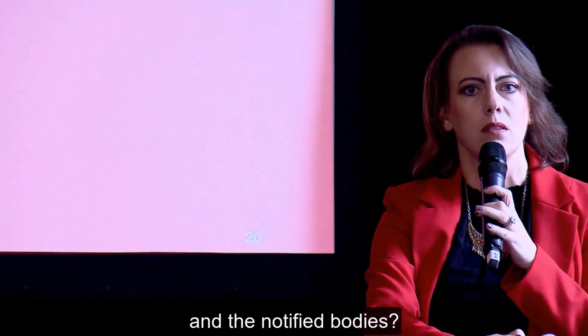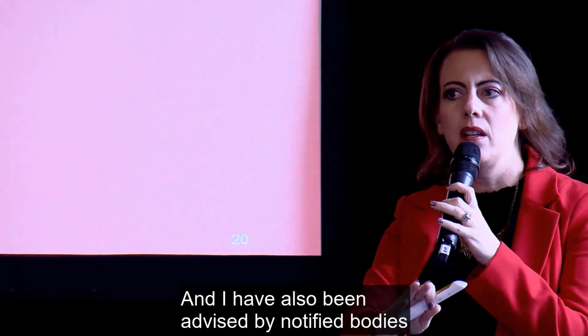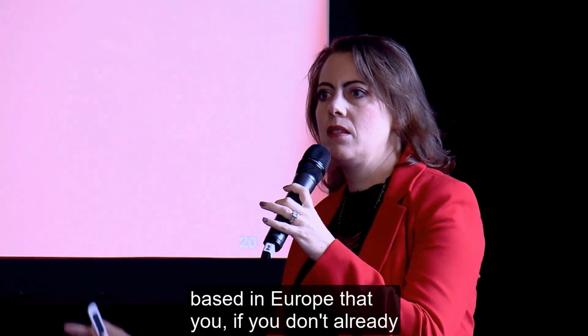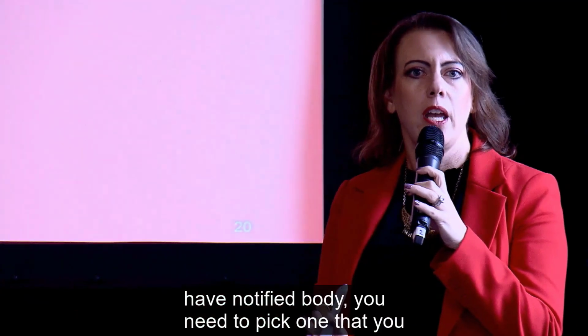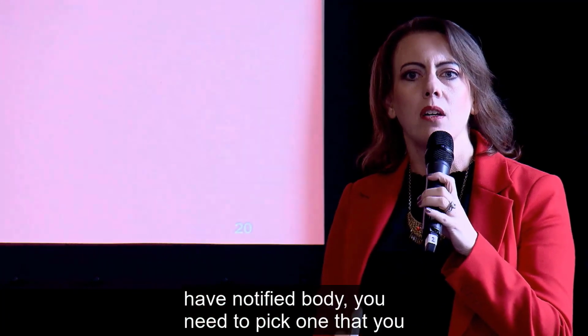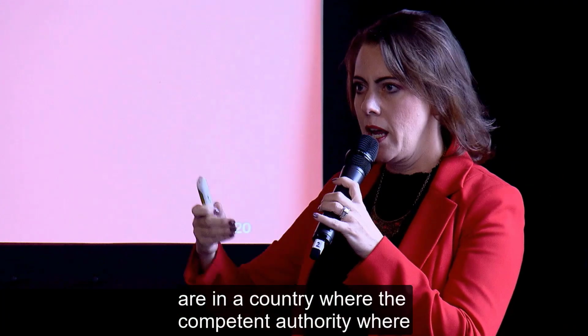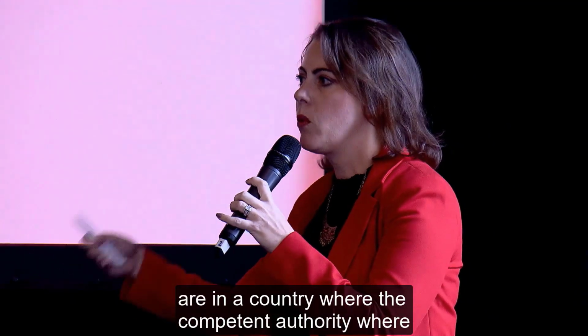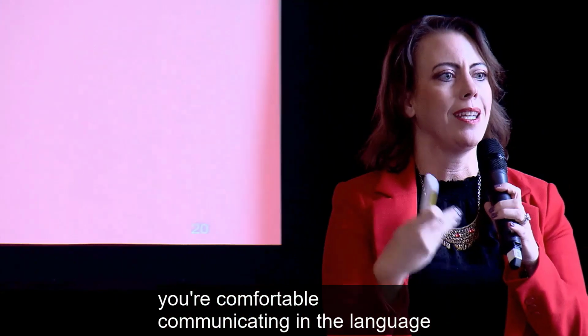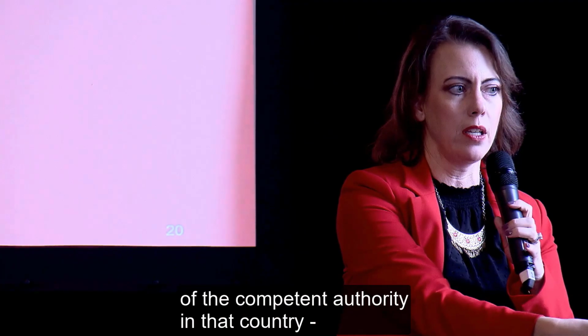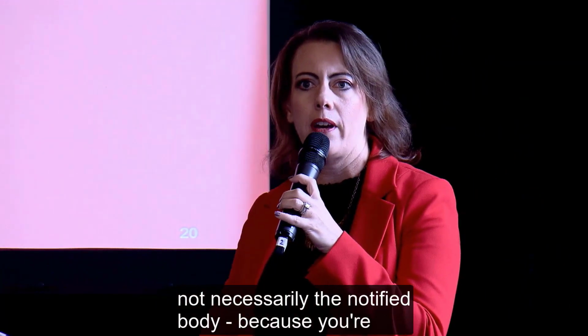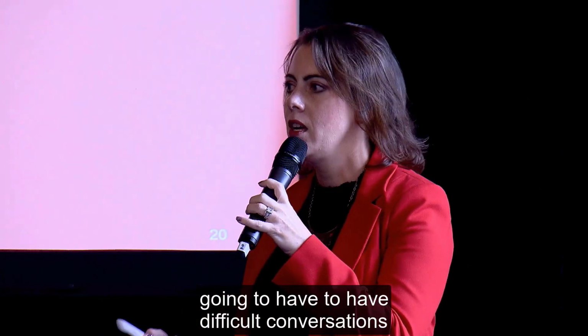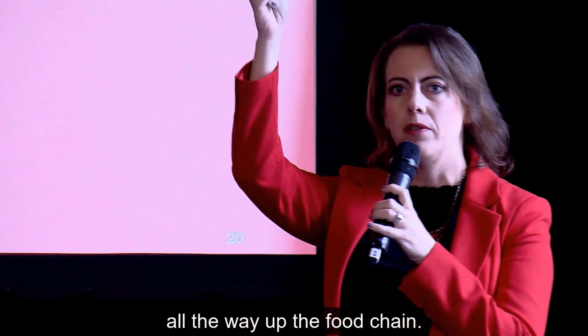the notified bodies? And I have also been advised by notified bodies based in Europe that if you don't already have a notified body, you need to pick one in a country where you're comfortable communicating in the language of the competent authority in that country, not necessarily the notified body, because you're going to have difficult conversations all the way up the food chain.